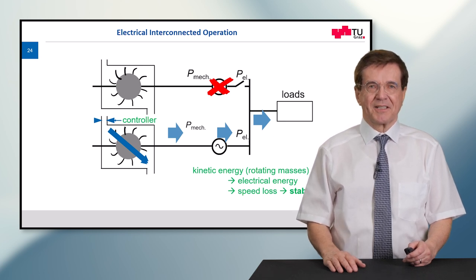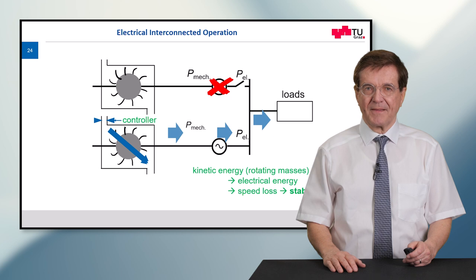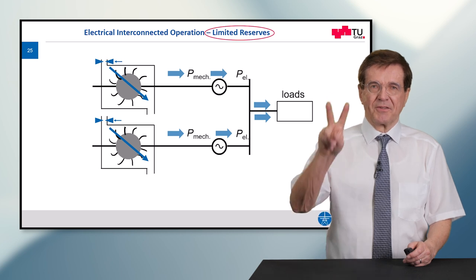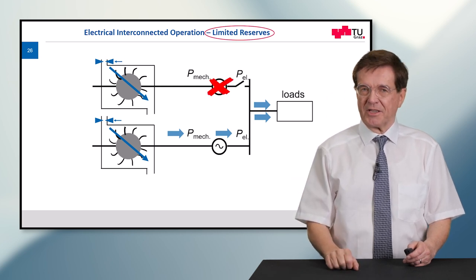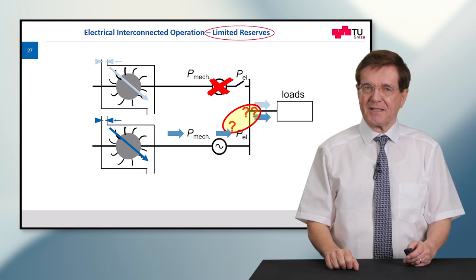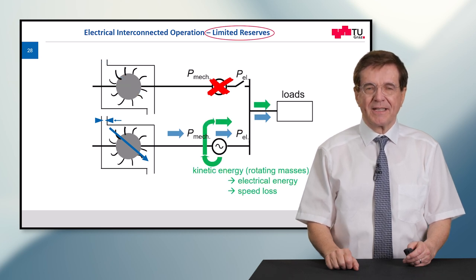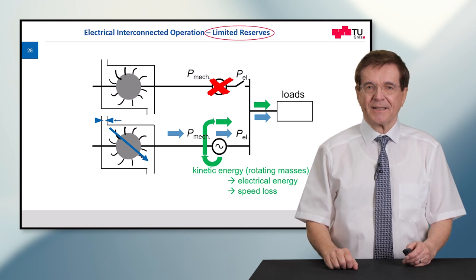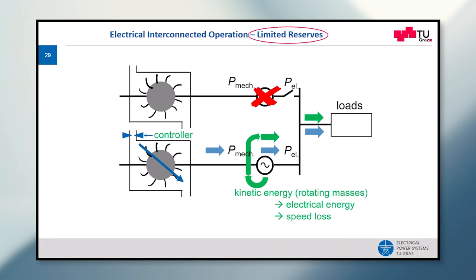Now we repeat the same process but with limited reserves. So again we have the two power plants running in parallel. One generator trips out. There is a deficit of power which is immediately recovered by the remaining generating unit, and again the speed is decreased. The controller again comes in, opens the valve.